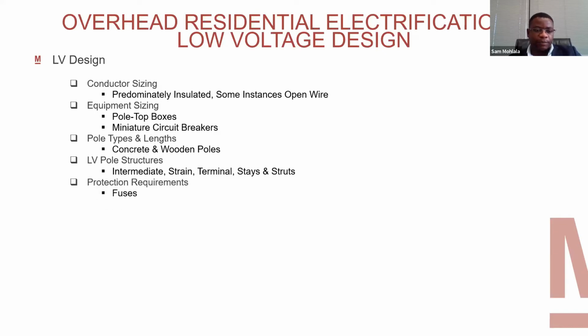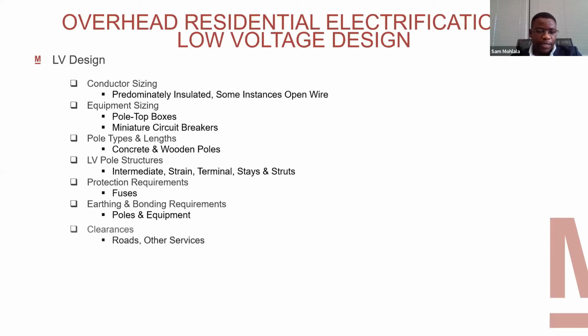Protection requirements: we normally use fuses to protect your feeders, so you also have to calculate the size of fuses to use for each feeder. Earthing and bonding requirements also depend on the supply authority, but most prefer the TNCS method, whereby your supply is earthed at the supply, and your earth and neutral are combined. Then you also have to take clearances into account.